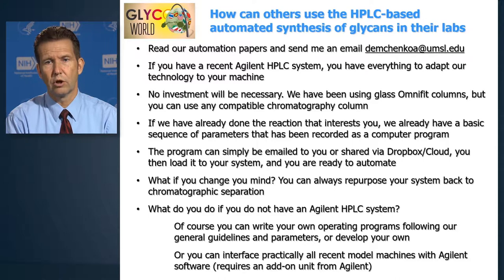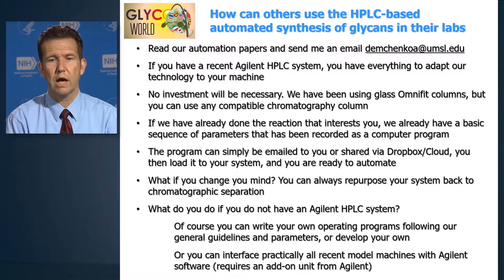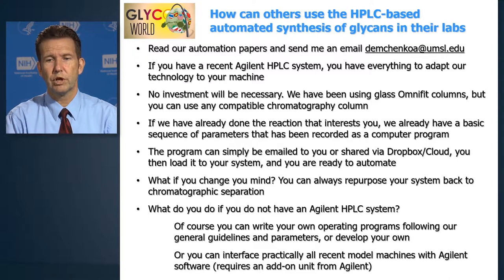How can you use this technology? I would recommend starting by reading our papers and maybe sending me an email for further information — the address is demchenkoa at umsl.edu. If you use an HPLC made by Agilent, you have everything needed to adapt our platform to your own needs. You don't need to add additional components — you can use what you have. We use glass columns, but you can use any chromatography column available in your lab. If you want to make a sequence that we've already made, it's very likely that we have a program ready for you, and you can also write your own programs. The program can be shared as a small file by email or Dropbox.